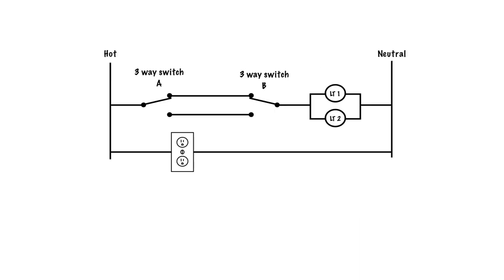The drawing we had previously I've converted to a schematic. I have my three-way switch here, my three-way switch here, my two lights, and my receptacle down here with a hot and a neutral coming in. Power comes into our common, then it goes up through the switch to a traveler. We have two travelers at a three-way switch, then our wire goes over to the second three-way switch where again we have two travelers, a common, and that common goes to the lights.